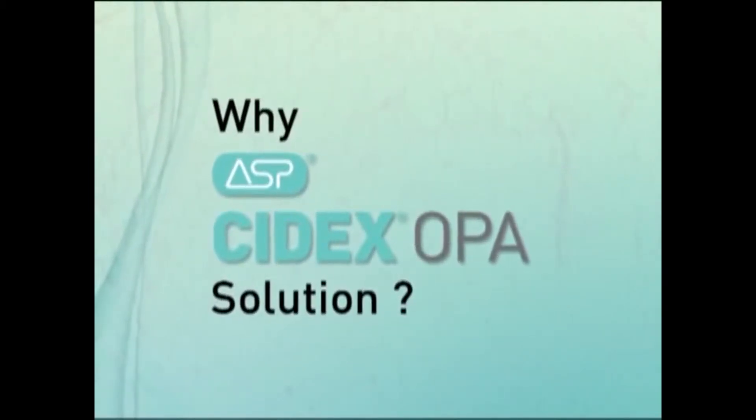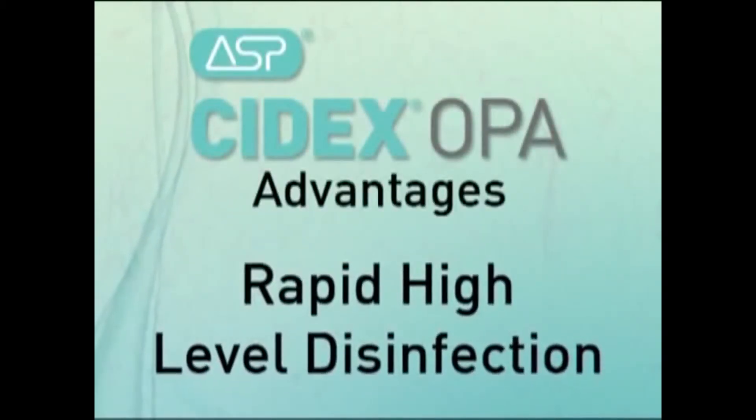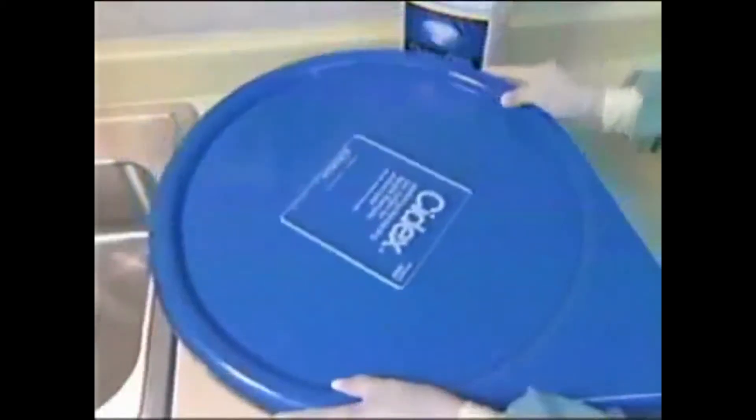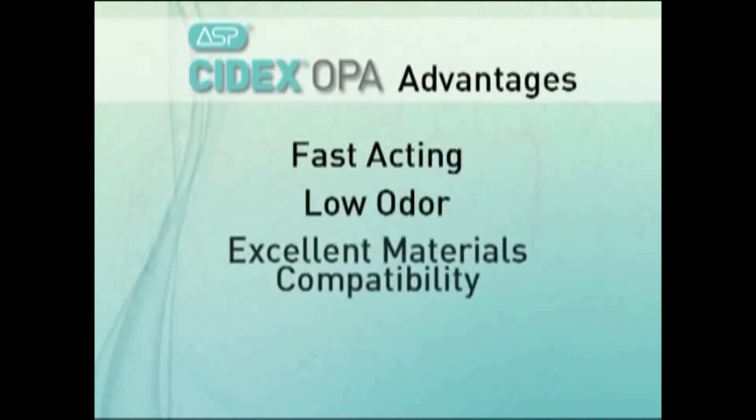Why Cidex OPA solution? It offers many advantages. Cidex OPA solution achieves rapid high-level disinfection in only 12 minutes, which allows for a fast instrument turnaround time. It has low odor, excellent materials compatibility, and ease of use, requiring no activation.